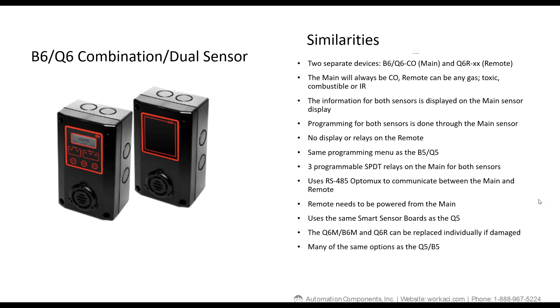So we can go into the differences between a B6 and a Q6. Basically, the obvious one is the B6 is going to be a BACnet MSTP protocol. The Q6 is going to be either RS-485 or Modbus RTU to a building automation system, or the proprietary Optomux protocol to one of either the M controller or the Q controller. The one big difference between the B6 and the Q6, compared to the Q5s and B5s, is that the B6 and the Q6s will not have any analog output. So if you need an analog output, like say a 4 to 20, you'll have to go back to the Q5s to get that. And sometimes that plays a factor in which units you can use and which ones you can't.